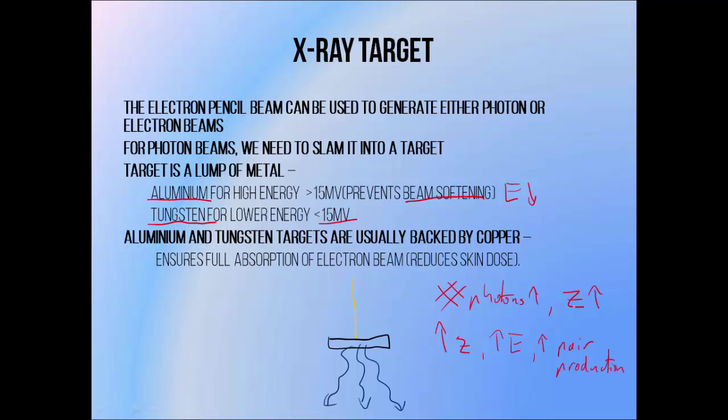So in a dual photon energy machine, as most linear accelerators are, each photon beam energy will have a separate target. Targets also tend to have a copper backing, which ensures that all of the incident electron pencil beam is absorbed. This is important because it is pointed directly at the patient, and any electrons making it through the target are going to result in unnecessary dose to the patient's skin. When using linac photon beams the goal is generally to treat deep structures, so skin dose is undesirable.